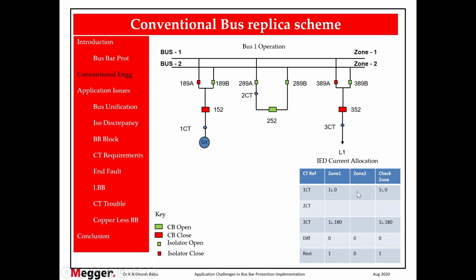89B is open, so nothing is reading in zone 2. The check zone is independent of the isolator. Therefore, both these currents are reading in the check zone. Why is this 2CT not reading in the check zone? 2CT is actually not the incoming or outgoing current. It is a circulating current within the substation. So the incoming current of the substation should be equal to the outgoing current of the substation. Kirchhoff's law, that is what we are following.